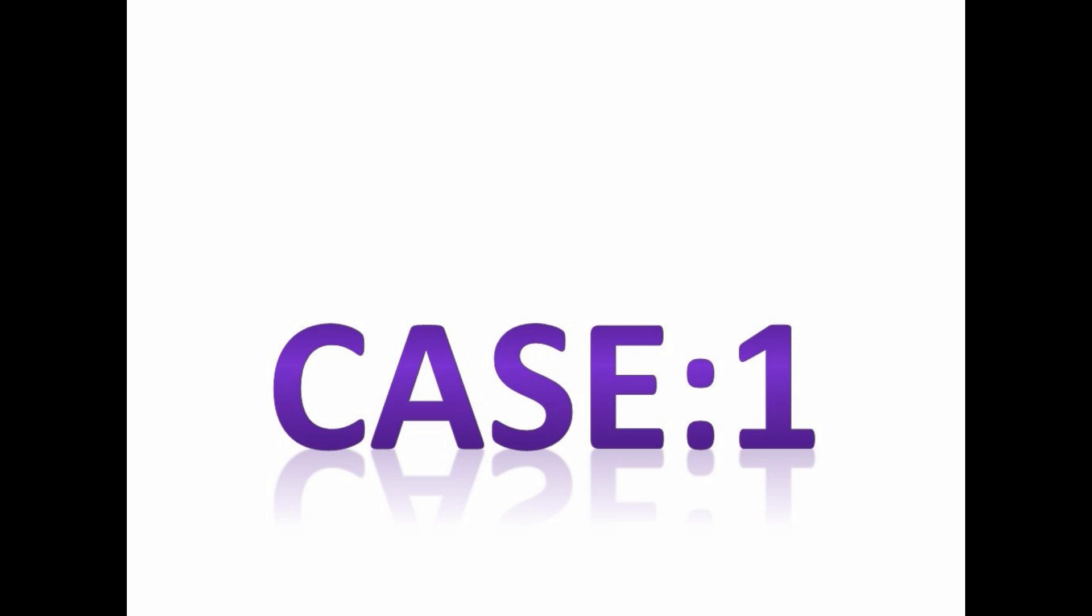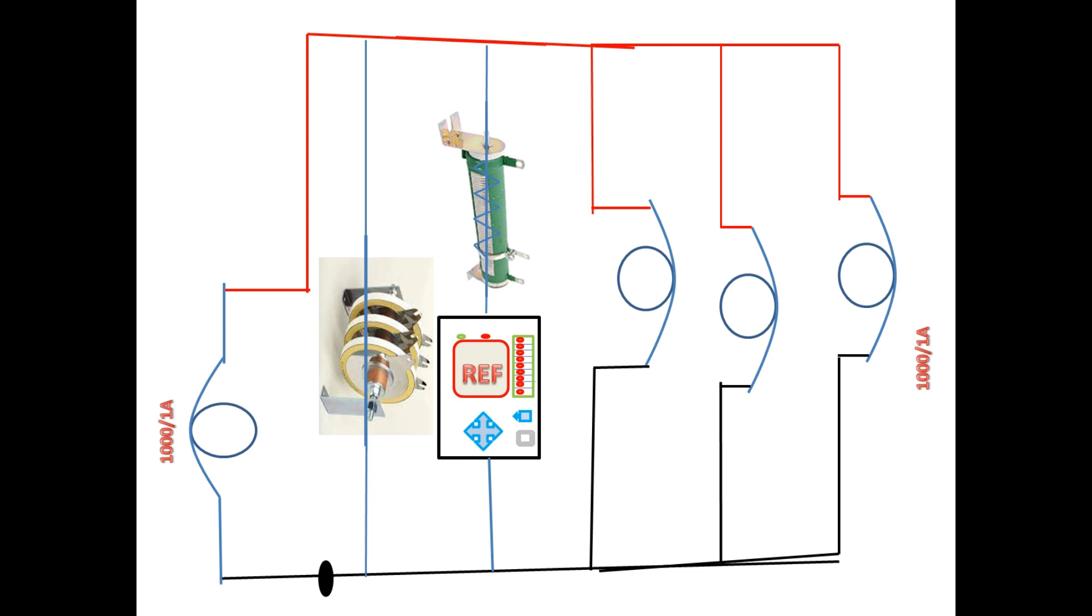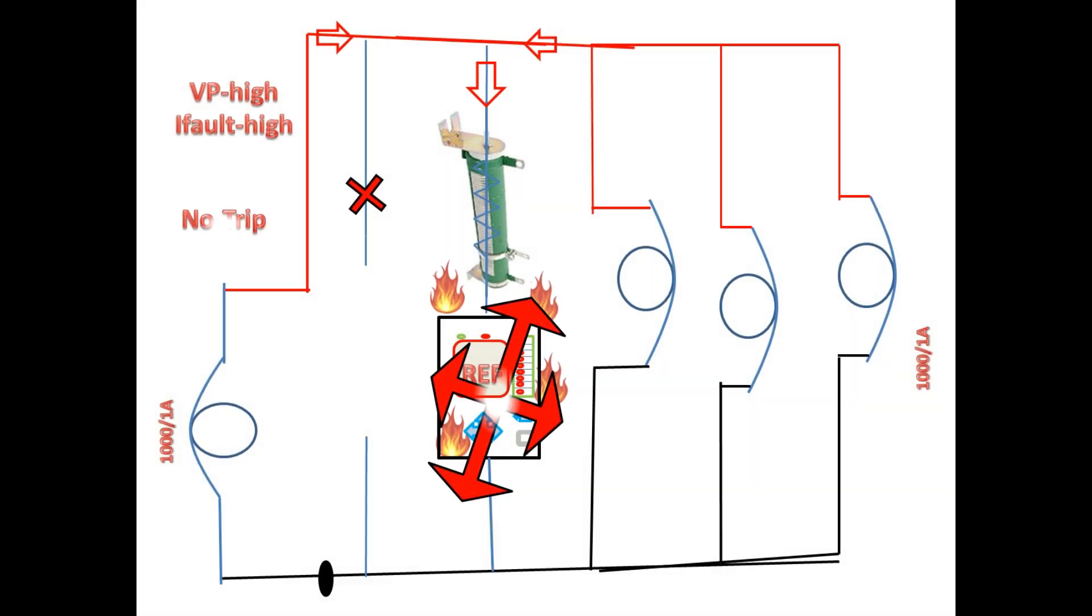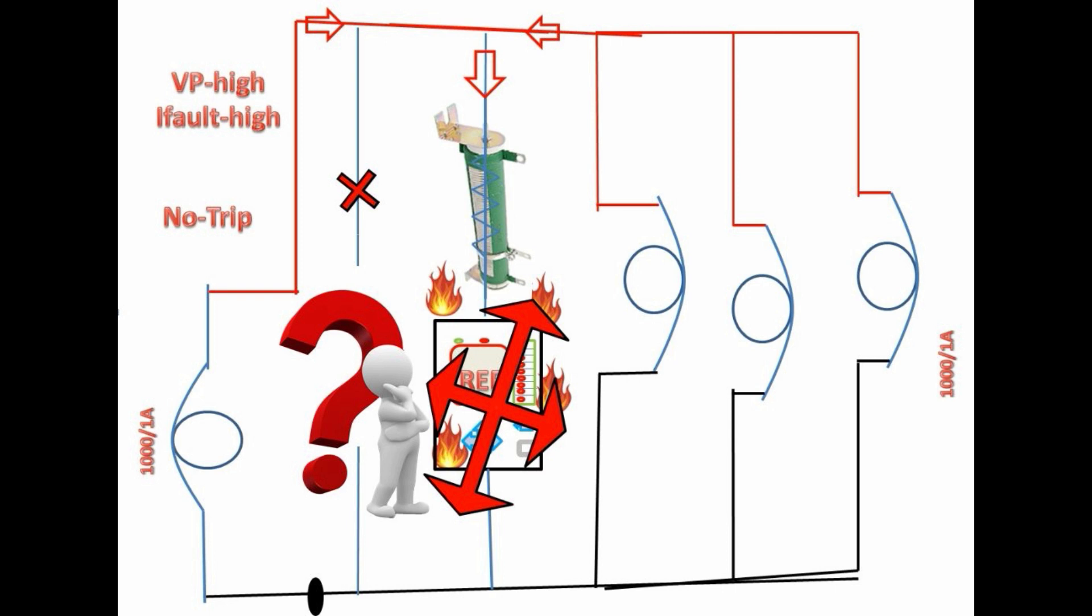Case 1. We consider we are not having a metrosil resistor in this case. We get a maximum internal fault condition. During this time, the fault current on secondary will be more than 20 times. That is for 1000 amps in primary and we get secondary as 1 amp. But during the heavy fault, we may get more than 20 amps in secondary. But this secondary current cannot be able to hold by numerical relay. And also during this fault, VP also will be very high. So the relay will have the chance of getting damaged by this. We came to know metrosil is very very important. Because if the relay gets damaged, then the protection of the device will be in question mark.